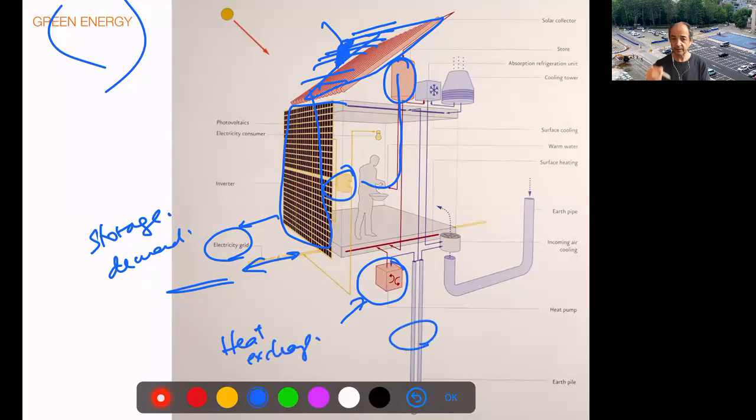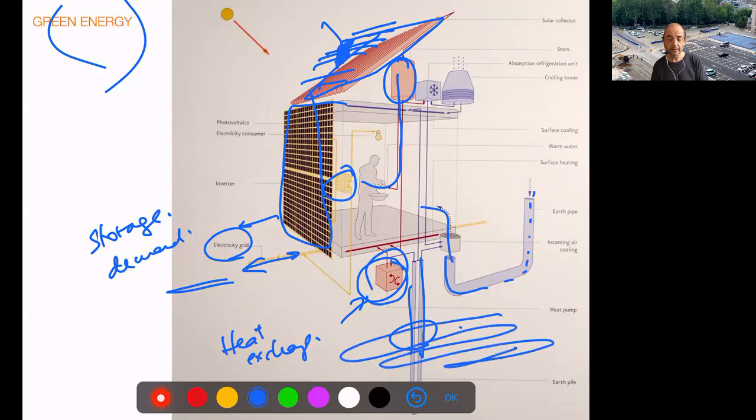In this case, for the geothermal, there are two versions of geothermal. The very deep one, when you go to the layers of the ground, where we have a lot of energy stored, right? And you can send a cooling or heating fluid with a very high specific heat, so you can store a lot of heat and exchange it for your system, and you can cool and heat. Or you can use the simplest, just cooling the air through the basement and pushing it inside. You can have something in between, with that water fluid going just 1.5 or 2 meters underground, and that will also give you some help.